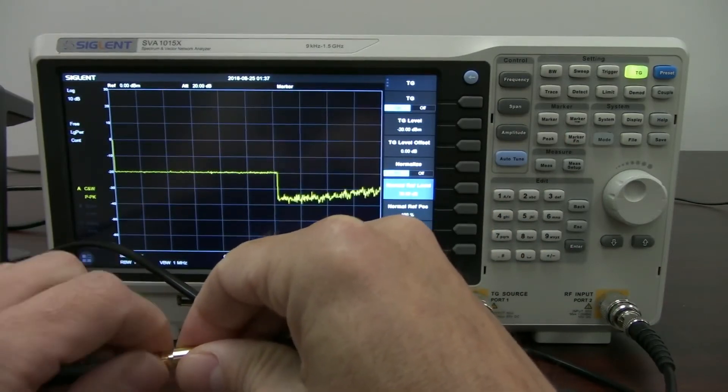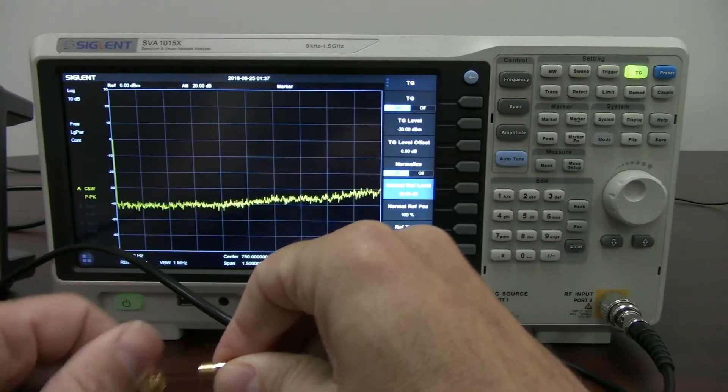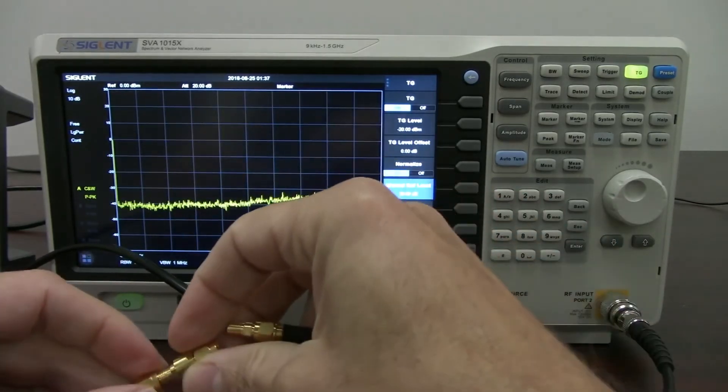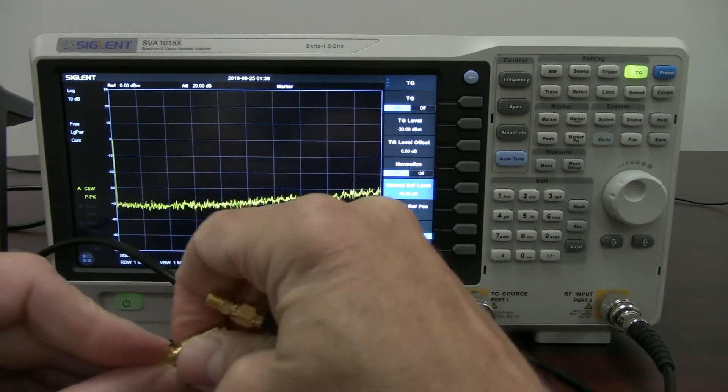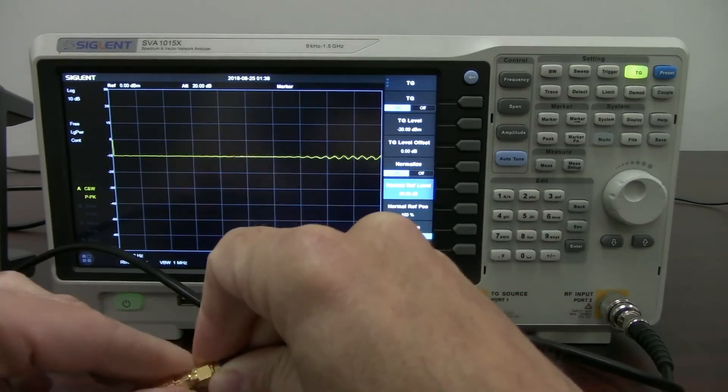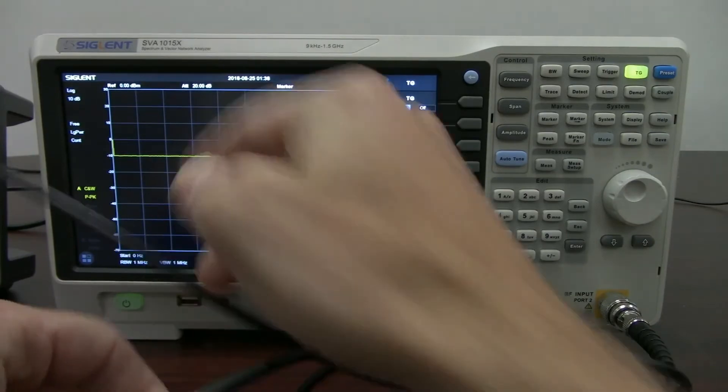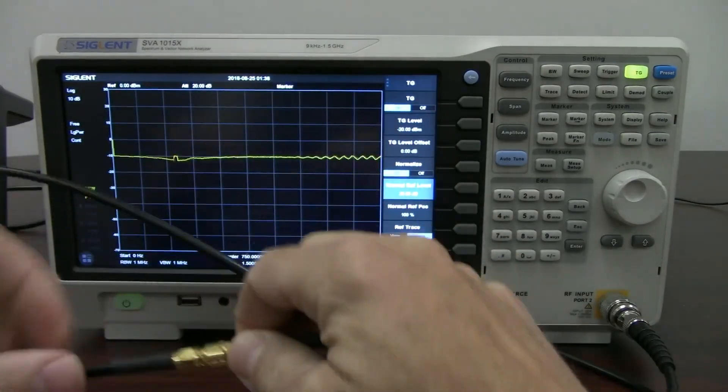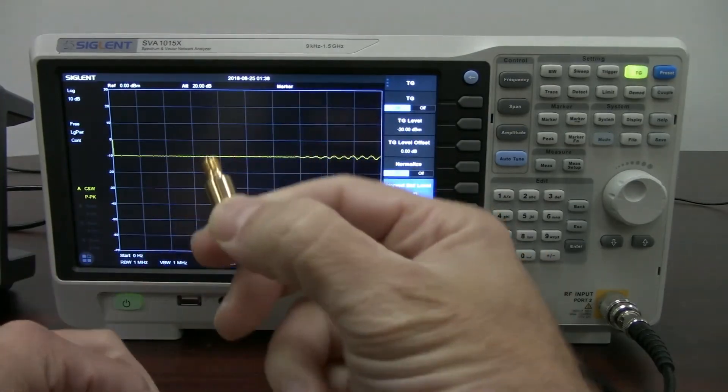And just replace that really quickly with this other one. Make sure that it is truly a 10 dBm attenuator. Here we go. And there we are. So we've got this at minus 10 dBm. So we now have characterized our attenuators, or at least verified that they are correct.